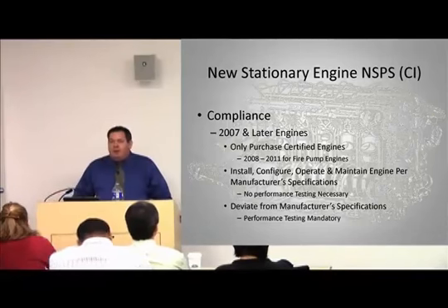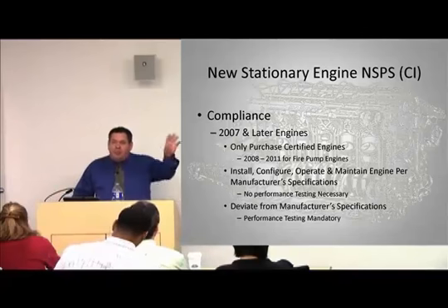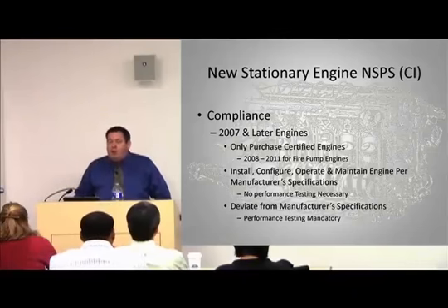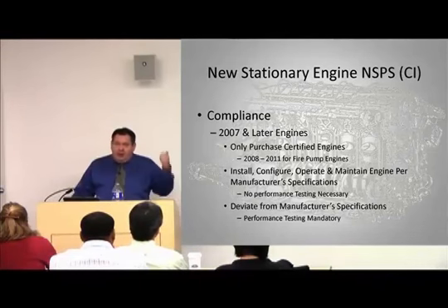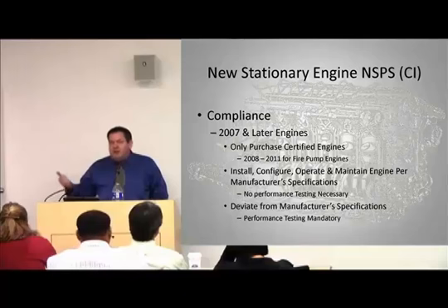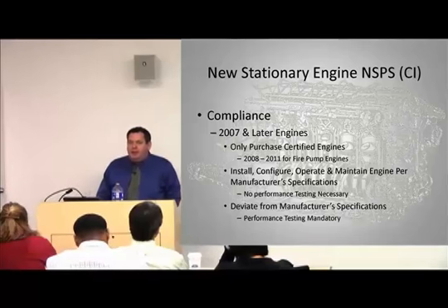Where it becomes a problem is under the NSPS for some engines at major sources and all engines at area sources. They're requiring a certified engine. So if you put in a non-certified engine, even though it meets the emission limits, you're going to be subject to further performance testing. Some of them are just going to be initial, some of them are going to be initial and either semi-annual or annual.